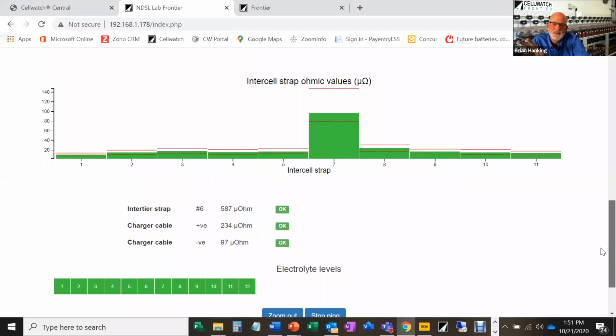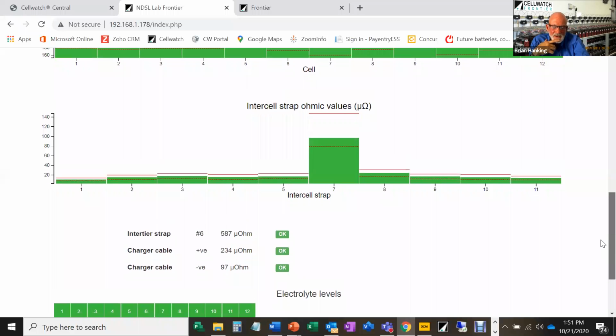The core of the system itself is tested, proven, and very effective. We can measure intercell strap ohmic values, which are pretty small values in that respect, so usually we're checking whether a battery has been torqued up correctly.